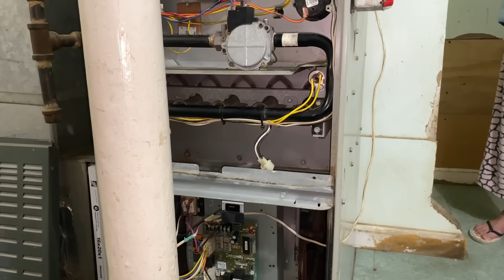The purpose of a filter is to keep the ductwork and system clean. When you have a dirty filter, try to breathe through a mask - it's hard, right? Imagine running a marathon wearing a mask, you can't, because it restricts your airflow. If I restrict airflow in a furnace, that high temperature sensor is going to get too hot. It'll turn the furnace off, then it'll short cycle - run for a little bit and turn off, run for a little bit and turn off. Here it wasn't even running at all. So your husband was wrong, but you need to keep the filters clean.